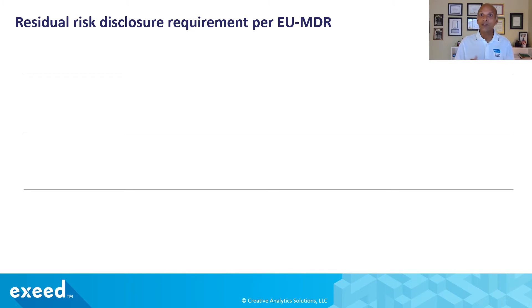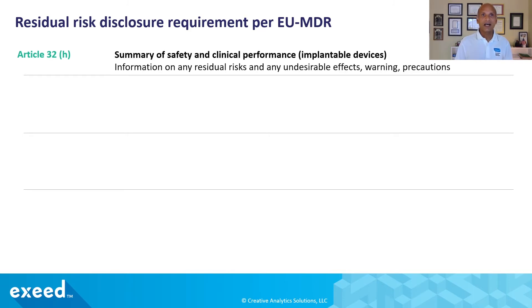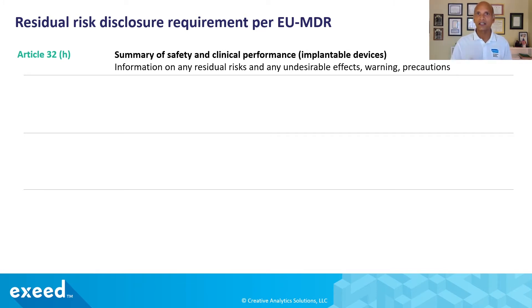Now let's look at what EU MDR, which is a regulation — a law — requires. In Article 32H, summary of safety and clinical performance for implantable devices, there is a requirement for information on any residual risks and any undesirable effects, warnings and precautions. Note: 'any' — not just significant. They want any residual risks disclosed.